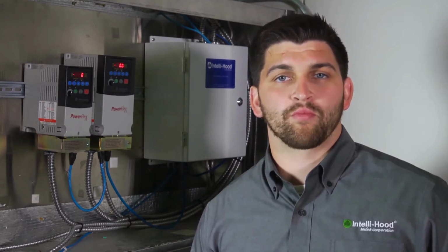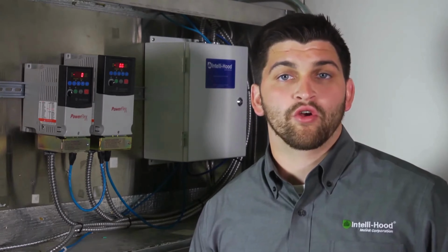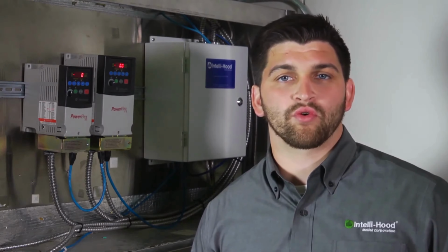In most cases, when a problem occurs with a fan, you have noticed because the kitchen is noticeably quieter or getting hot and smoky. To check the connections here, you'll need a multimeter to check DC voltage and continuity. You may want to have your facilities or electrician look into the issue.